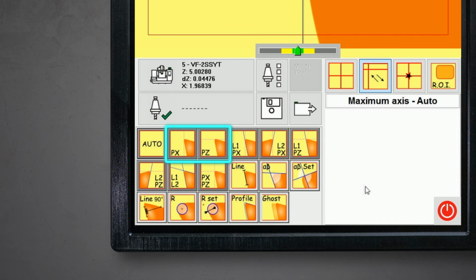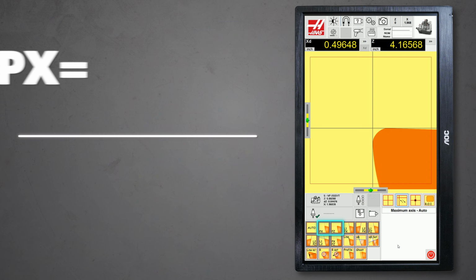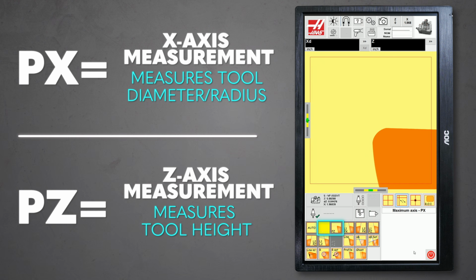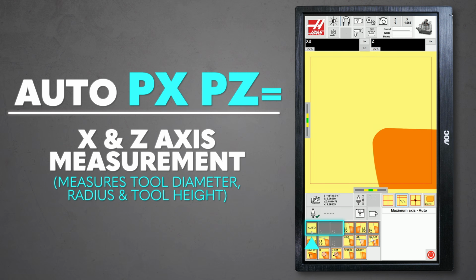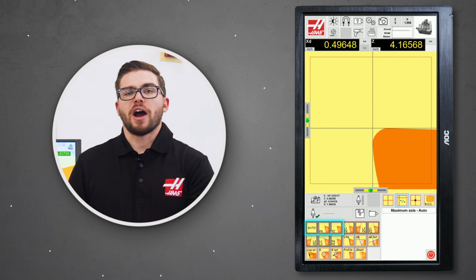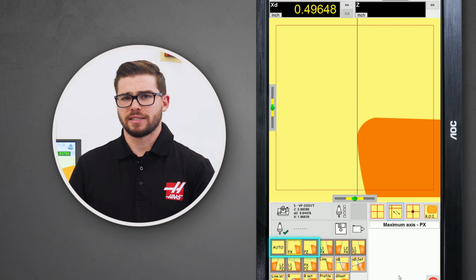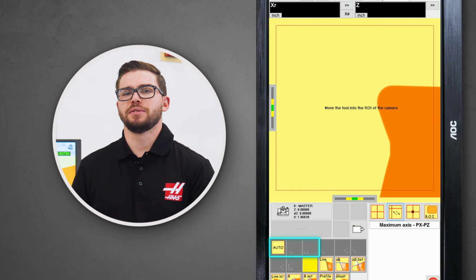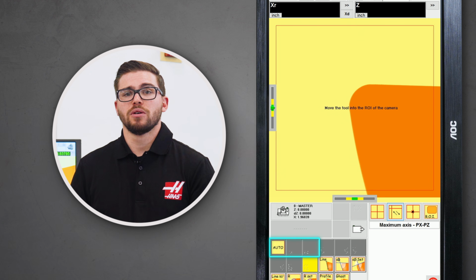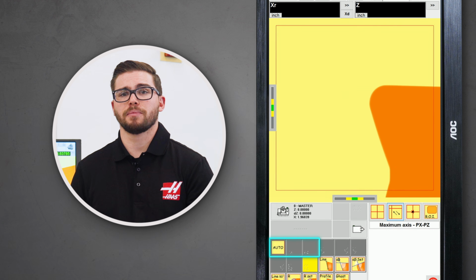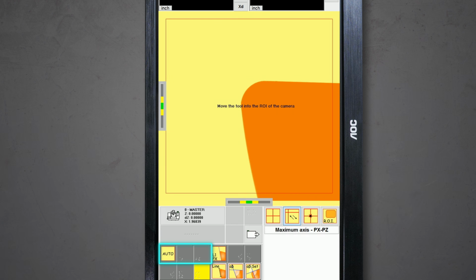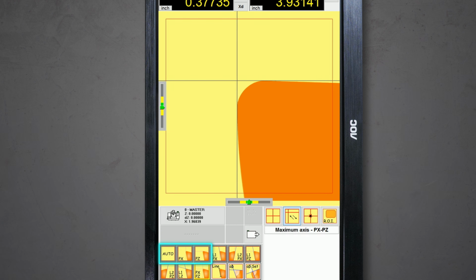I covered the PX and PZ functions earlier, but I'll review them real quick. PX and PZ are fairly self-explanatory, as PX measures only the X-axis and PZ measures only the Z-axis. Auto and PX-PZ are the same as they measure both the X and Z axes. If either of these is selected and only one axis is being measured, it is most likely due to either the tool being out of focus or there not being a diameter or tool top to measure. Simply rotate or move the tool to solve this issue.